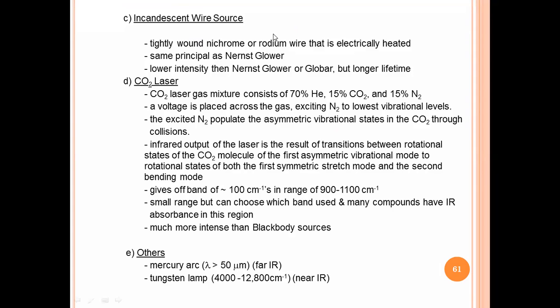Another lamp radiation source used is an incandescent wire source - tightly wound nichrome or rhodium wire that is electrically heated. Same principle as Nernst Glower. Only difference is in the material used as a source. Same principle but lower intensity than the previous two radiation sources.